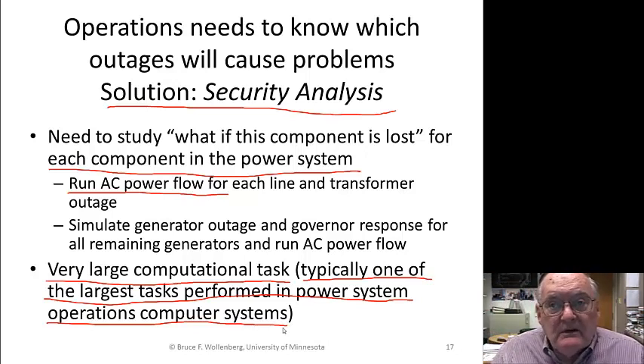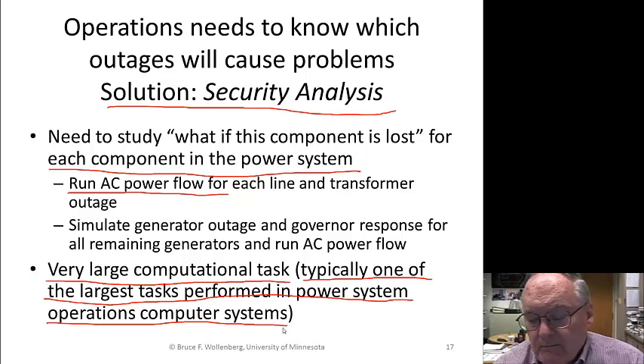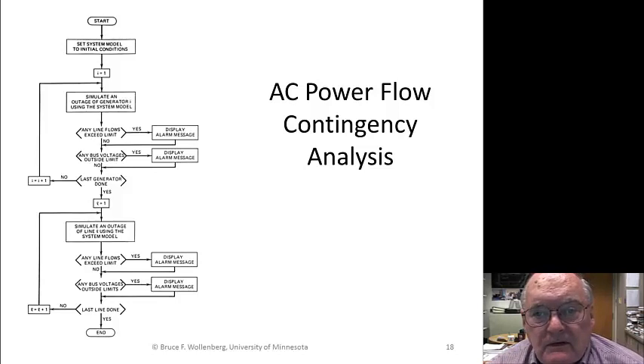The other one, by the way, is the alarm processing, making sure that everything gets compared to a limit and then brought out to the operator. So those two functions are both kind of in parallel for keeping the system secure. Here is the overall flow chart of it. System conditions we get from the state estimator. Simulate an outage of generator I using the system model. Any line flows, give me an alarm message. Any bus voltages, give me an alarm message.